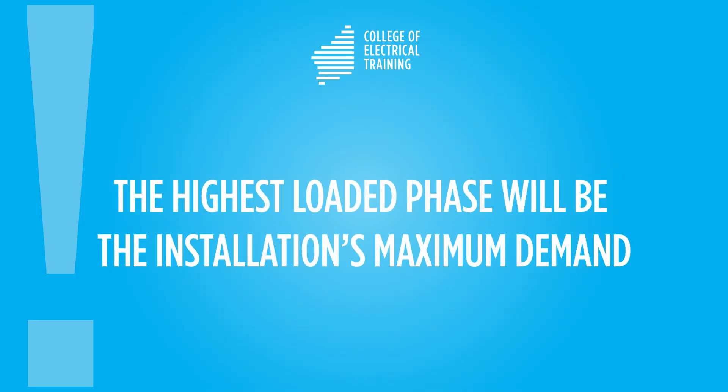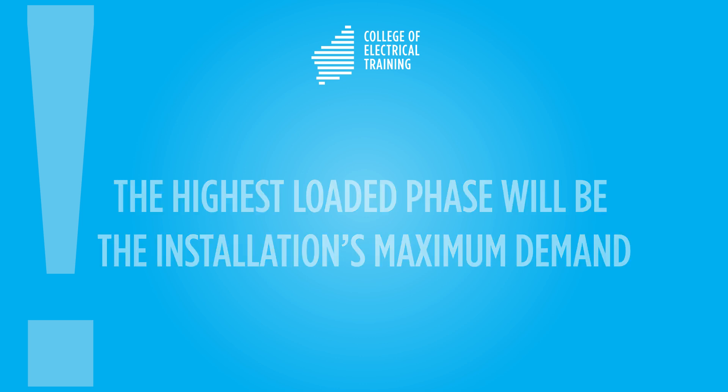In a three-phase installation, each phase is considered separately, relating to individual load groups. Some single-phase loads may be present in one phase and not in others, while any three-phase load will contribute to all phase loadings. Remember, the highest loaded phase will be the installation's maximum demand, so balancing phase loadings as closely as possible is an advantage.